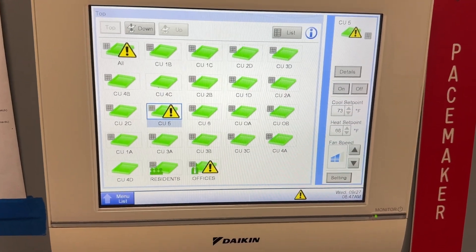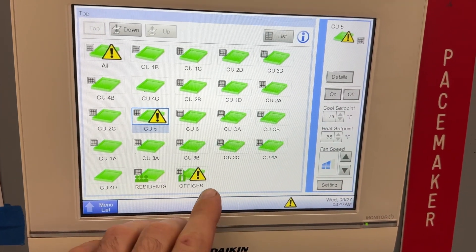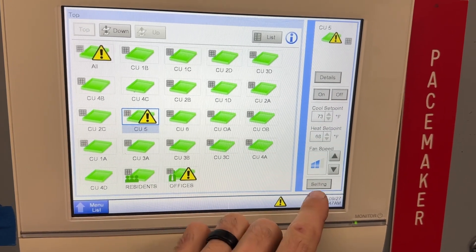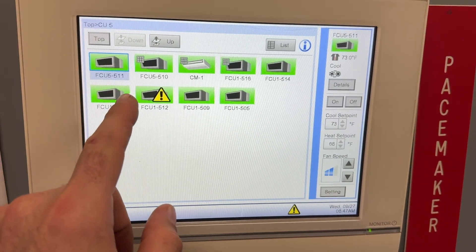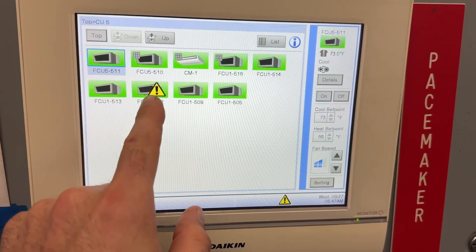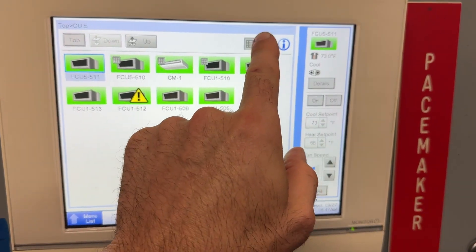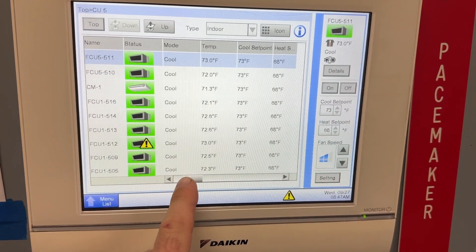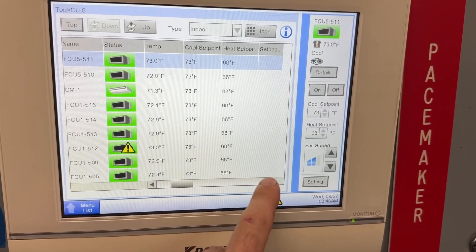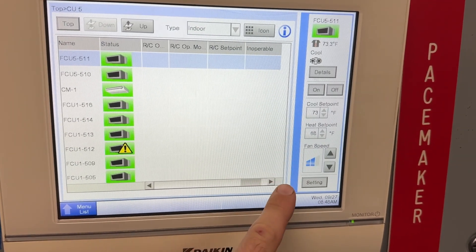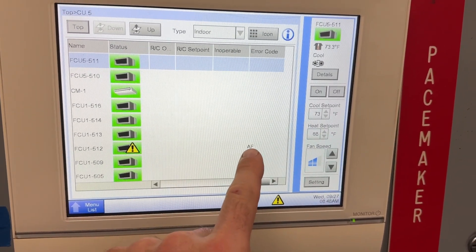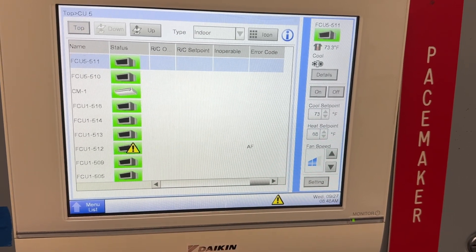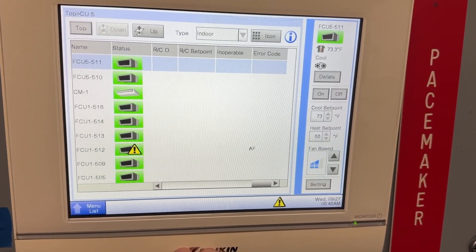This is the ITM for a Daikin VRV3 system and you can see I've got a system alarm here. We'll go down. These are the indoors and you can see it's only this one here. Go to list and then just try and drag that. This thing's stubborn. There's my error code AF and that has to do with condensate issues.